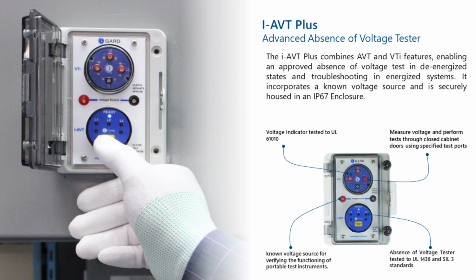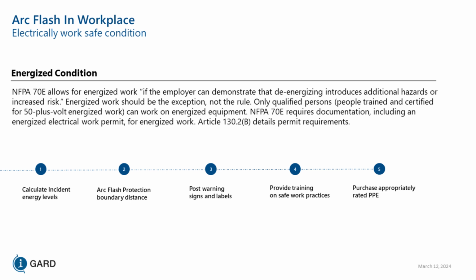These 2 points come from a source inside the AVT, and the AVT is listed to UL 1436 and IEC 61508 to meet SIL 3, safety integrity level, and it's a strenuous test to perform. The AVT is powered by the voltage on the bus, but it has an internally charged supercapacitor, which is your power source for the indicating lights, because you need power when the system is de-energized. NFPA 70E allows energized work if an employer can demonstrate that de-energizing introduces additional hazards.